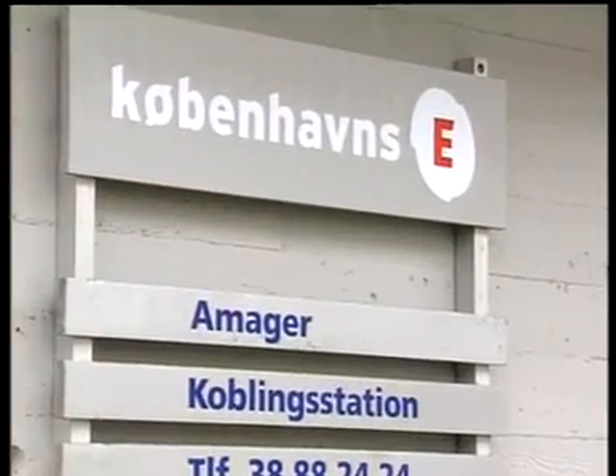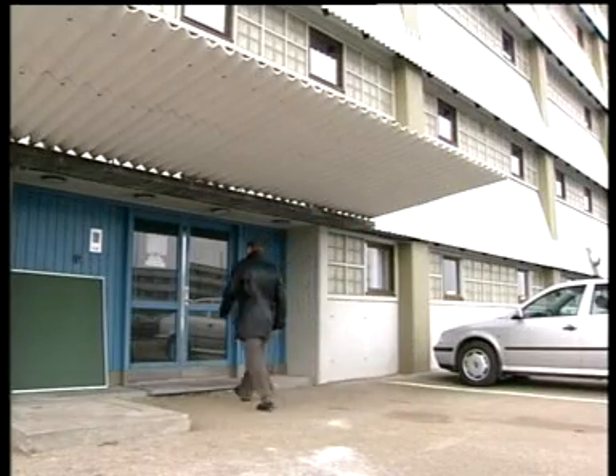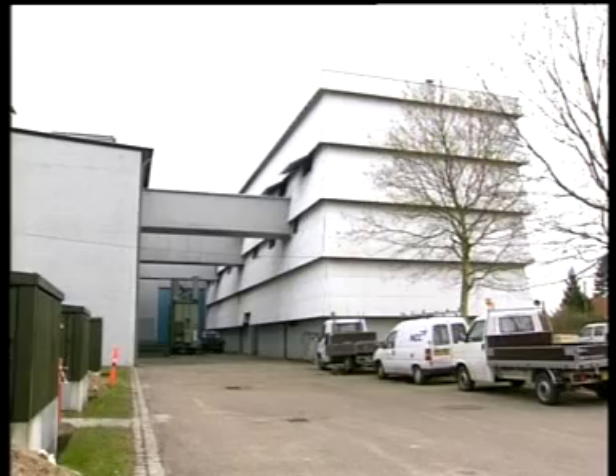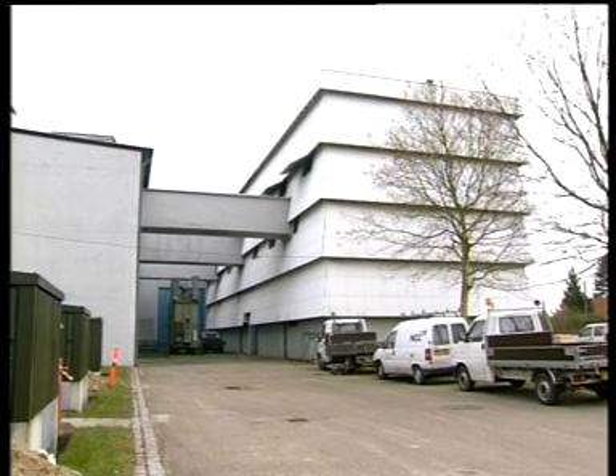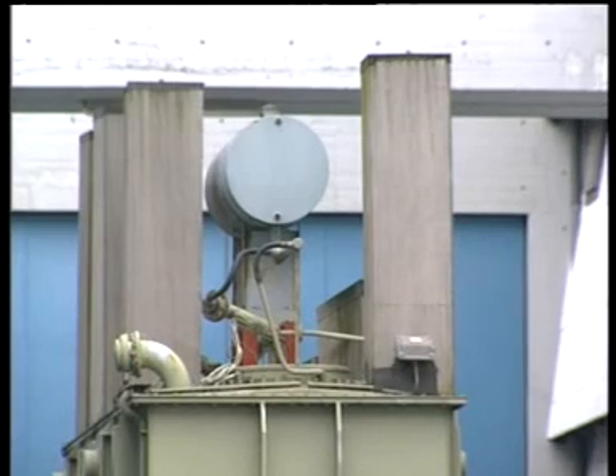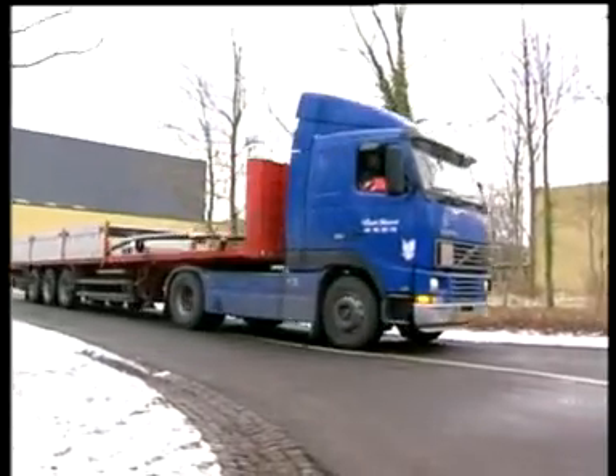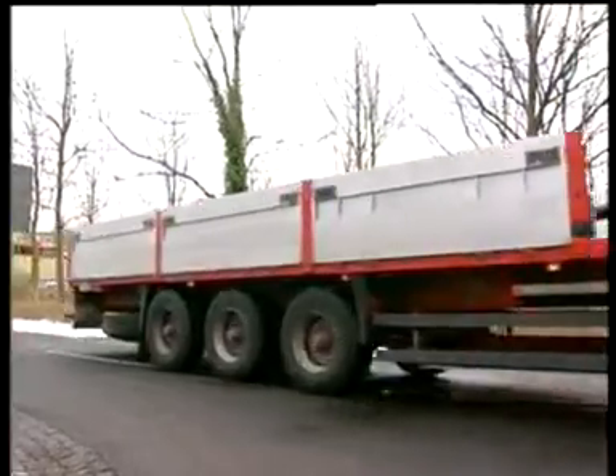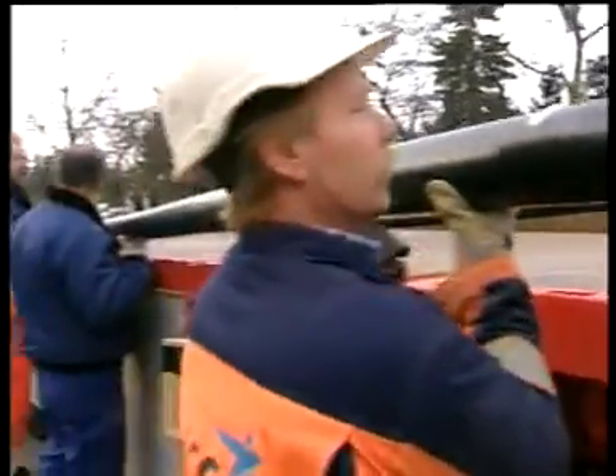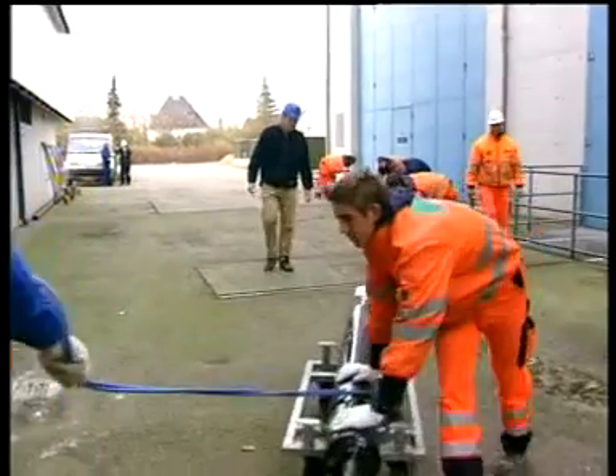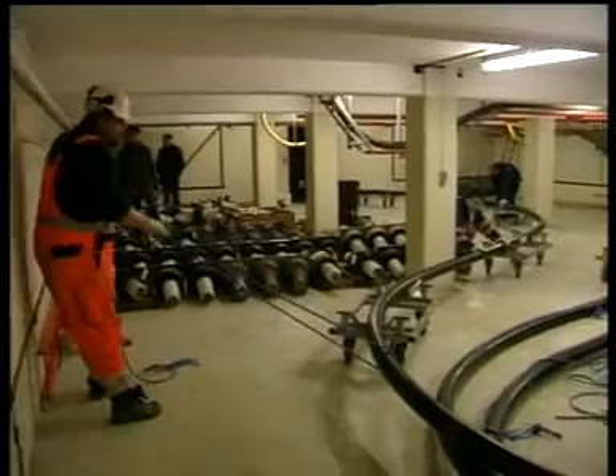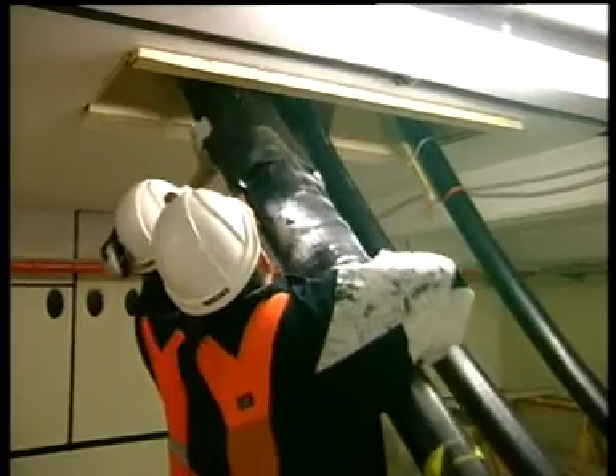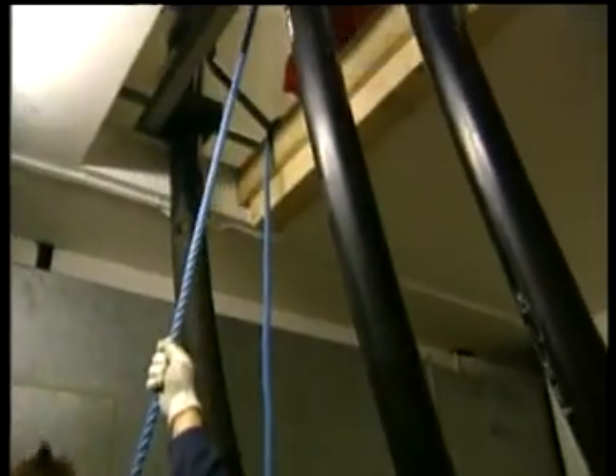The first installation of an HTS cable system in a public network took place in February of 2001 in a substation that delivers electricity to approximately 50,000 residents on the island of Amager, just outside Copenhagen. At 8 o'clock this morning we started to load the truck at DTU Institute, and then we drew the cable to the substation at Amager and started to pull the cable in position, and we finished, I think, about 11:30. At that time the cable was pulled into position, and this afternoon we start to install the end termination.